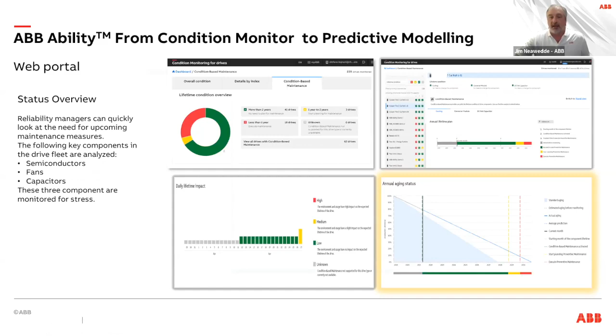The last graph takes this analytical information and gives us the capability to predict what the aging is. The standard aging curve is shown here in the blue triangle, because this particular drive was being well taken care of. We're able to estimate its lifespan and show, with the yellow line, when it needs some preventative maintenance. The red line is when the system is going to need to be replaced.